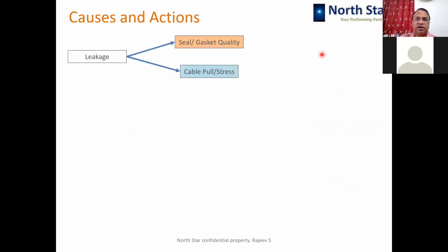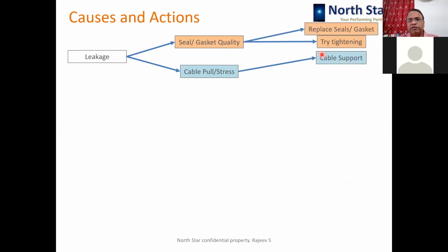There are different causes for leakages, and there is no rocket science here. There is the seal and gasket quality, which causes the leak. Second, the cable or the overhead conductor coming to the bushing causes a pull on the bushing, and that causes the failure of the bushing. So replacing the seal is the long-term solution. That is the only long-term solution.